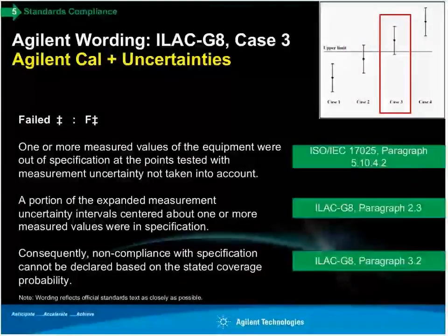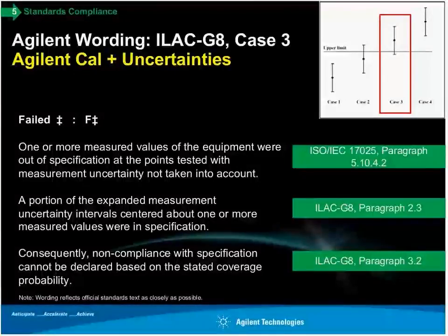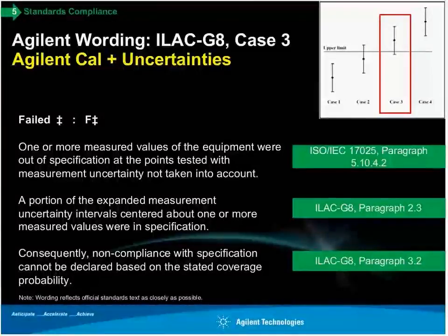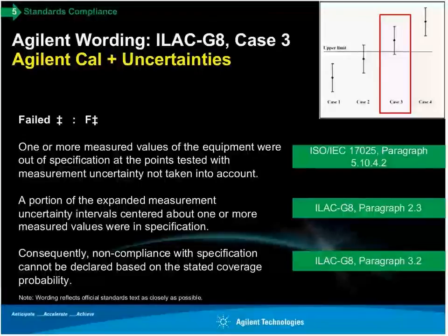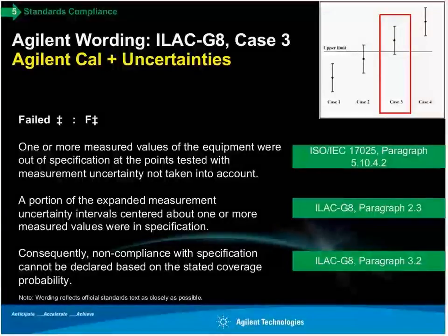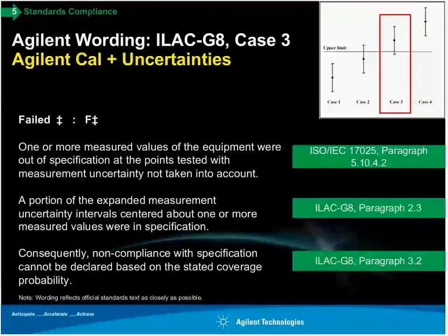Okay, this is an example of case 2, and as for case 3, when we look at reporting failed results, the same 3 scenarios apply that we saw on the previous slide with 17025 and ILAC G8. But when we look at 17025, one or more measured values of the equipment were outside of the specification at the points tested, with the measurement uncertainty not taken into account. But when we look at the next step, a portion of the expanded measurement uncertainty intervals centered about one or more measured values were in specification.